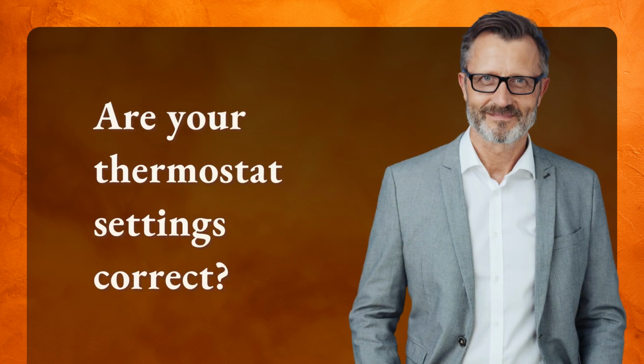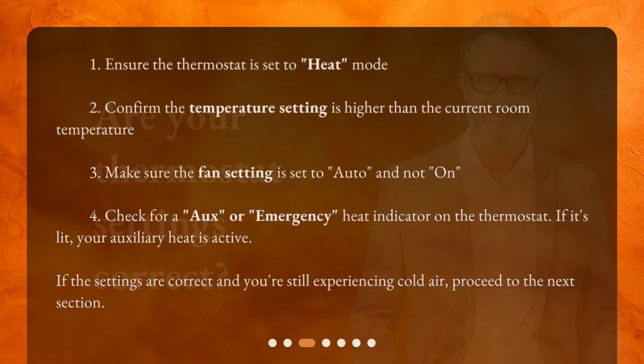Are your thermostat settings correct? 1. Ensure the thermostat is set to Heat Mode. 2. Confirm the temperature setting is higher than the current room temperature. 3. Make sure the fan setting is set to Auto and not On. 4. Check for an AUX or Emergency Heat indicator on the thermostat. If it's lit, your auxiliary heat is active. If the settings are correct and you're still experiencing cold air, proceed to the next section.